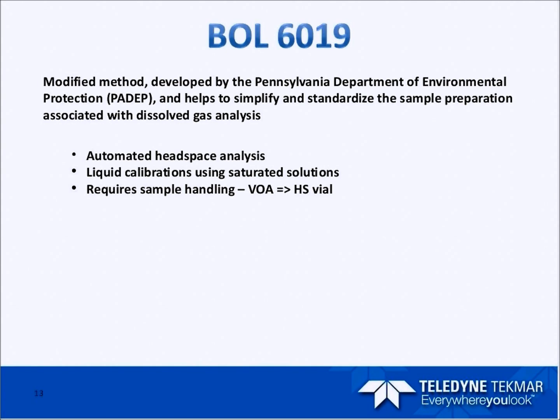And it uses liquid calibrations, which seem to be more real world. Using a gas standard, which some people do in the RSK175 analysis, there can be a little bit of a disconnect in your response potentially, because you're dealing with liquid versus gas. It just seemed a little bit strange to us to do a calibration in a different matrix than the sample itself. So this was something we wanted to look into on our own.